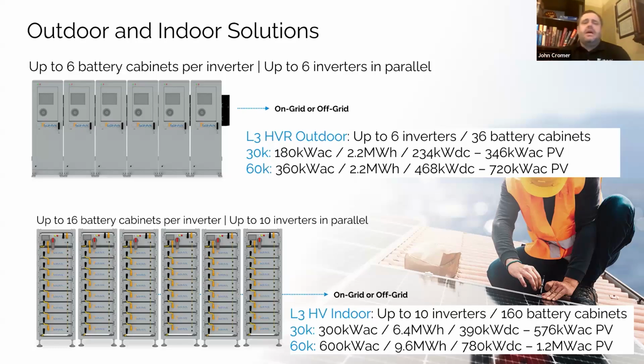So as you can tell, we can go up to 300 kW of backup capability on 208, and that'll pretty much back up any 208 service. Then when you get to 480 volt service with 10 inverters, that gets you up to 600 kW of backup. If you need more than 600 kW of backup capability with 480, you would essentially be installing multiple systems on the same site, and they would be backing up different parts of the facility independently.